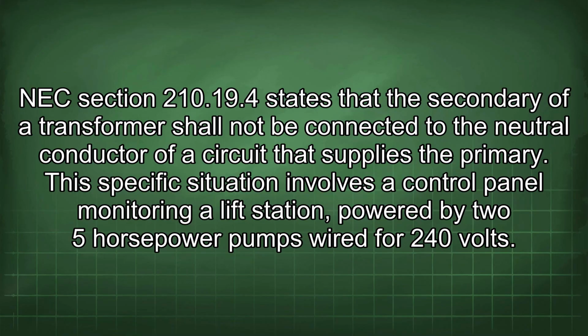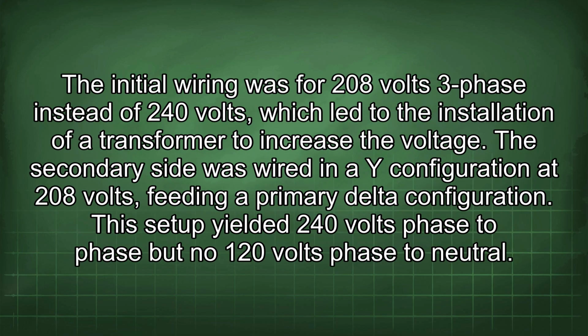NEC section 210.19.4 states that the secondary of a transformer shall not be connected to the neutral conductor of a circuit that supplies the primary. This specific situation involves a control panel monitoring a lift station powered by two 5 horsepower pumps wired for 240 volts. The initial wiring was for 208 volts 3-phase instead of 240 volts, which led to the installation of a transformer to increase the voltage.